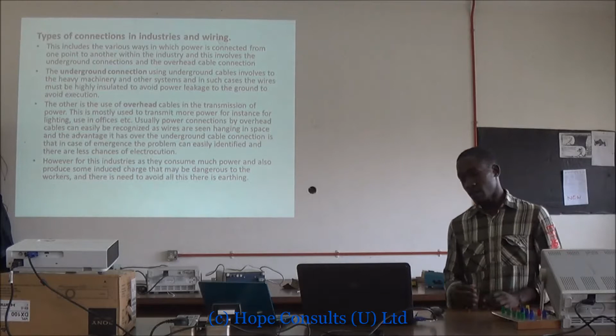As we have been talking about earthing, earthing is just a safety measure. The earthing of electrical equipment is a protective measure designed to protect us from electrical shocks by preventing the exposed conductive parts of the equipment from becoming live. That is, if any fault occurs, like an insulator coming off a wire and becoming in contact with the body of a machine, that can lead to a shock. The exposed conductive parts are things like the metal container housings, the cabinets, the control circuits, the metal tracking carrier cable from the cabinet to the machine, and the machine itself. That is what we have been talking about.